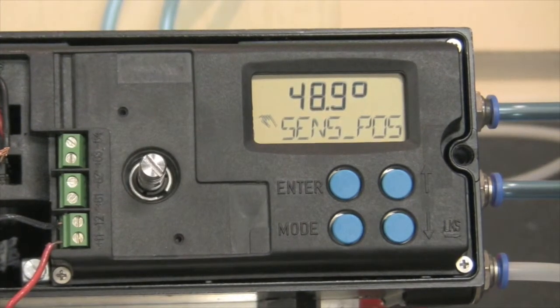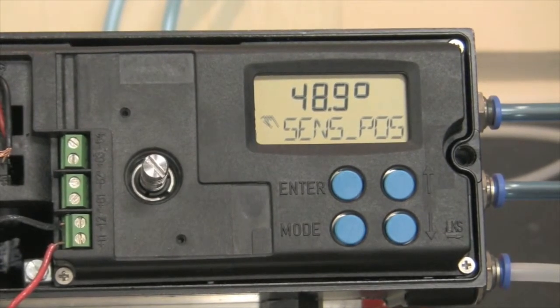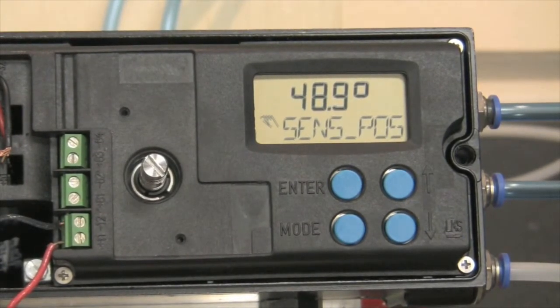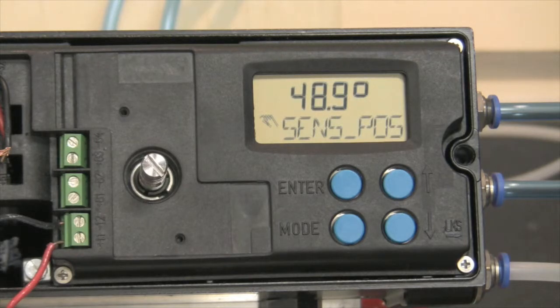Now to get the D400 back into the correct quadrant, we'll need to remove it from the actuator and make sure that arrow is pointing between the A and the B on the back of the positioner. We've already done that and reinstalled our D400 to the actuator. Now we're reading sense position again to make sure we're reading between positive 57 and negative 57.